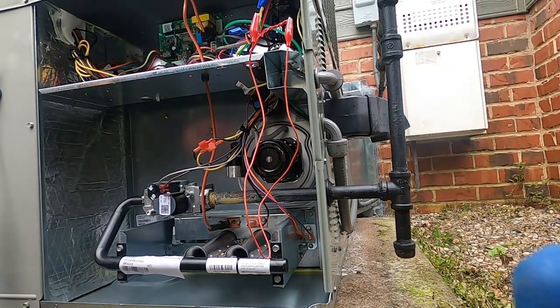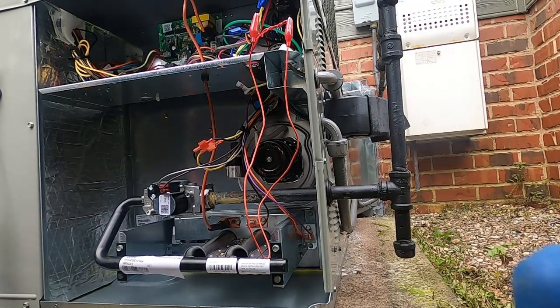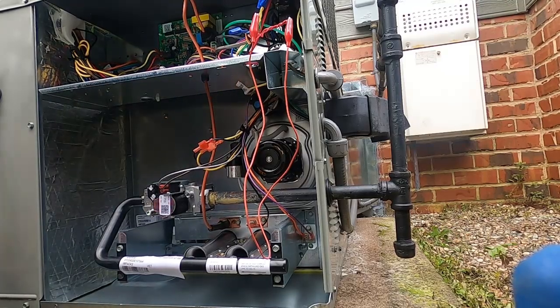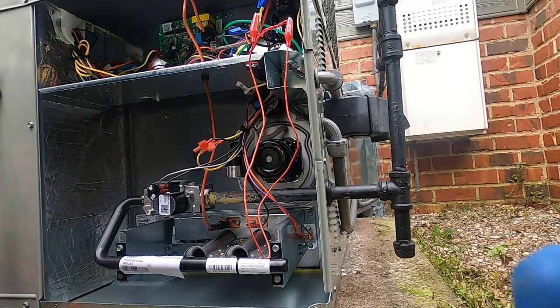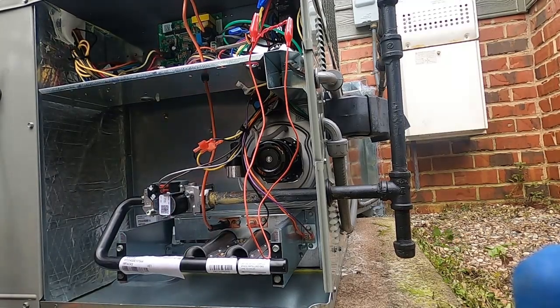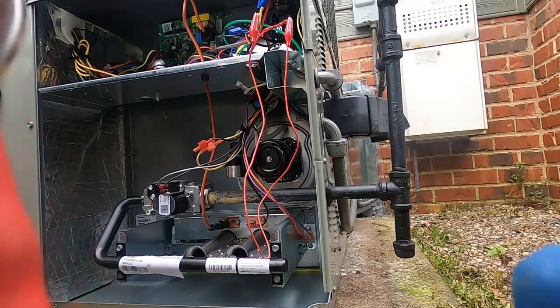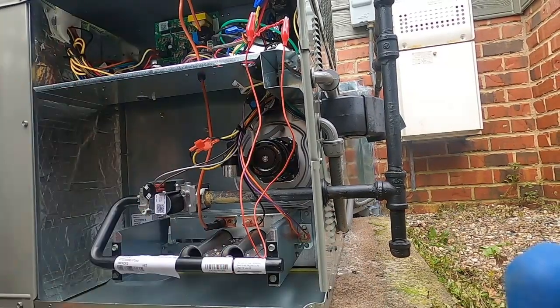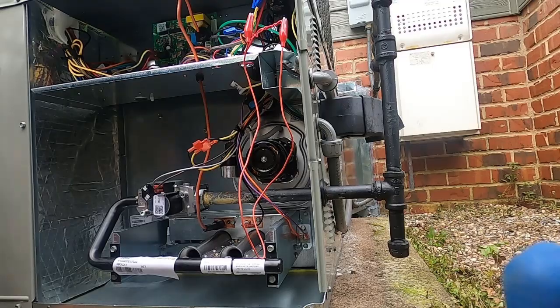It's just odd that they don't make you fill one of these commissioning forms out on every system you install, just when they make the decision to supply another new system to replace a newer unit that you're having problems with, and they can't get the part for it. It's just a bad part, basically. But they want to make sure it's set up properly, so it is what it is.